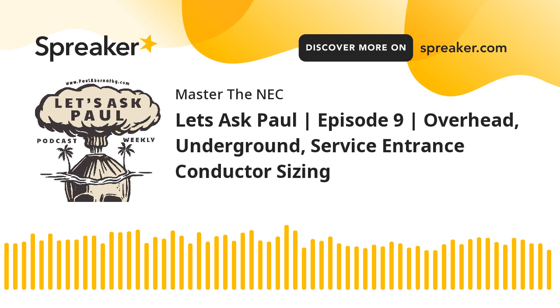All right, so let's go back now. In this case, if we're doing overhead service conductors, I'm back at part 2, at 230.23. I have to do a load calc, and I have to come up with that load calculation, whether I'm using the standard method or optional method, and I size my conductors accordingly. Once I know those conductor sizes, then when I'm sizing my grounded conductor, I first want to go to 250.24(C), which is ultimately going to send me to 250.102(C)(1), the table. Use those ungrounded conductors that we calculated using, again, standard or optional method, your flavor. And go down and see what is the minimum size of my grounded conductor that it can't be smaller than. And you write that down.